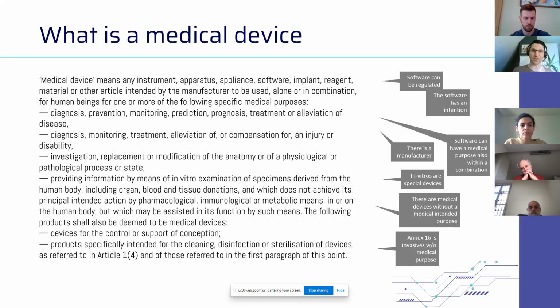By deconstructing that first sentence, we already see that software can be regulated as a medical device, and that a medical device has a specific intended purpose set by its manufacturer, meaning we don't create anything for fun, we create something with an intention. This intention is the intended purpose or the intended use, and we should be very careful with phrasing that intended purpose, because anything that comes to validation reflects back to this phrasing. Anything that you incorporate as technology needs to be compatible with the intended purpose. If it isn't, your validation fails or your product exceeds its definitions and your technical file is practically worthless.